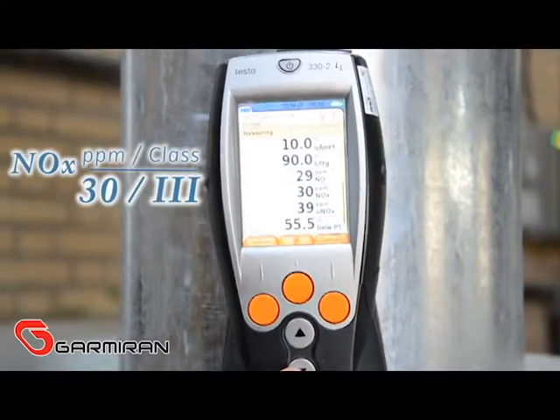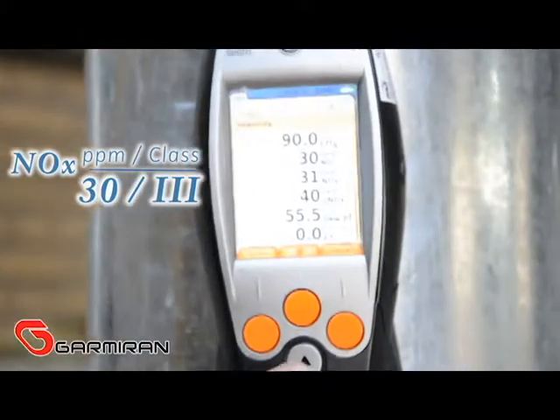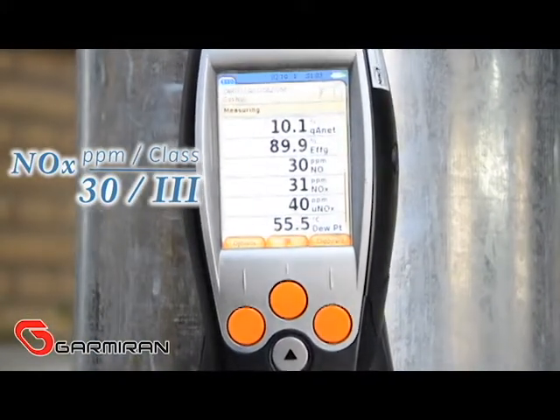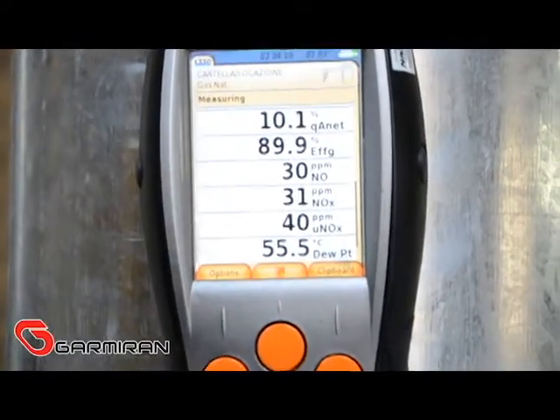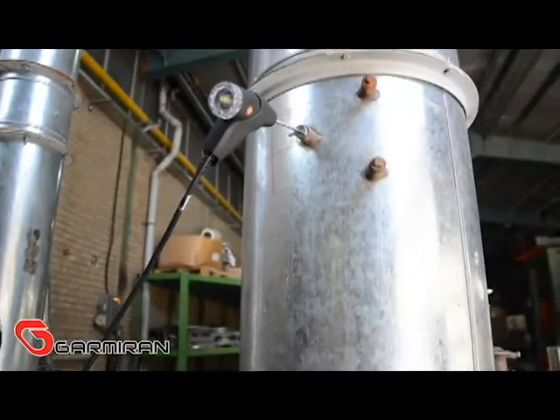The NOx amount of this burner is measured at 30 ppm, so this burner is putting it in class 3, which is the best class determined by EN 676 standard. This new design Garmiran burner can easily pass the requirements of EN 676 standard. Garmiran can meet customer needs and burner orders.